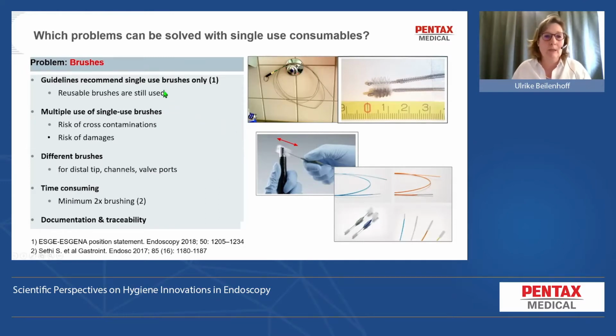guidelines nowadays recommend single-use brushes only, but there are still reusable brushes in use. And you see here these damaged reusable brushes. You also find residuals on the brushes. And even single-use brushes are used multiple times, which then cause, again, the risk of cross-contamination damages.